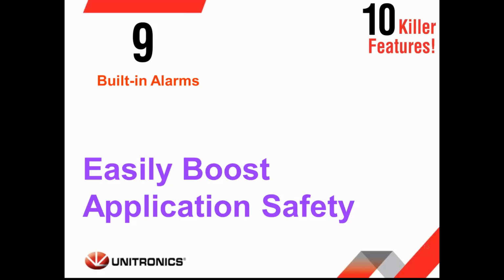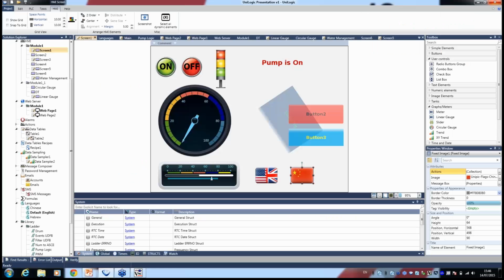Okay, now, I want to say that UniStream was designed to be a true multi-purpose, high-functioning controller. Okay, feature number 9, built-in alarms, is a very good example of this. The alarm system is designed in accordance with ISA standards for alarm systems and process industries. It's intuitive, easy to implement, easy to operate, and the system includes a lot of features that allow you to detect alarms, analyze them, and take action. Ophir, show us.